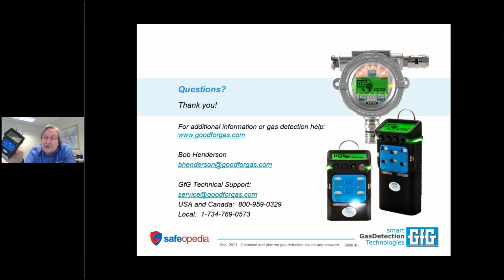Even if you're keeping sensors in an external so-called warm-up box, disconnecting the sensor even for a moment or two while you're pulling it out of the box and then putting it into the instrument allows that sensor to destabilize quite a bit. So by the time that you let it settle back in for 30, 40 minutes, you really do need to put it through a full calibration. By the time you do all that, that's a lot of effort just to reconfigure your instrument.